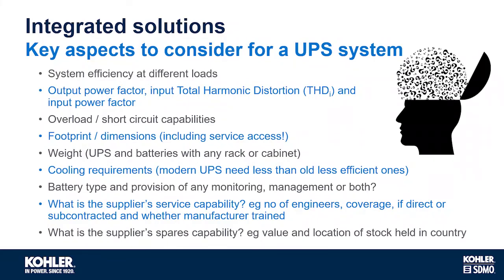With the battery, we have to understand what type of battery it is and what the use of that is. Like I say, typically they're standby VRLA batteries now. The battery is the backup of the UPS, so we should be managing that ideally, or at least monitoring it, to make sure that it's available. It's often forgotten and overlooked, but it's a very important part of the UPS system.